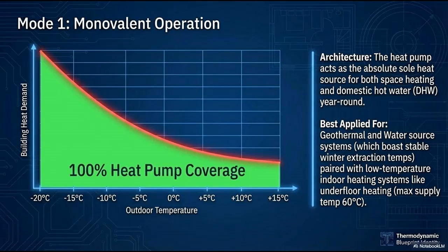Which brings up the absolute biggest anxiety for anyone living in an older house, because older homes usually have those massive, heavy cast iron radiators mounted to the walls. All right. And those old radiators require water heated to roughly 90 degrees Celsius to actually radiate enough heat. But earlier, you said heat pumps are designed for low temperatures. They operate most efficiently when making water that's only about 55 degrees Celsius. So does putting in a heat pump mean you have to hire a demolition crew to rip out every pipe and radiator in your house?